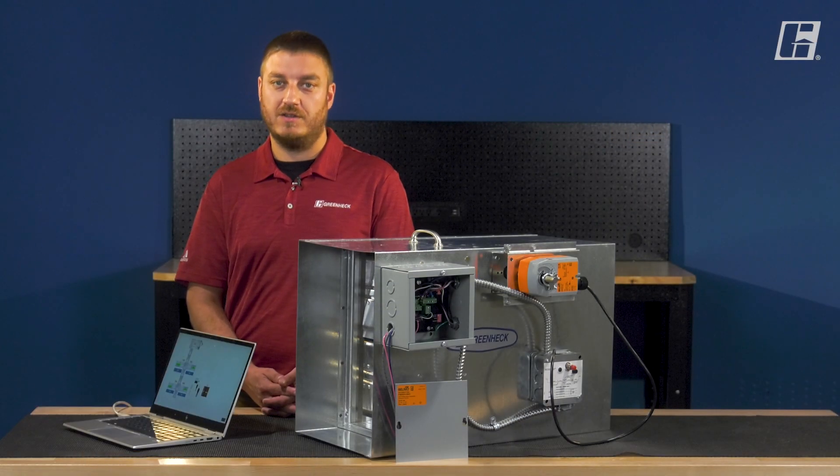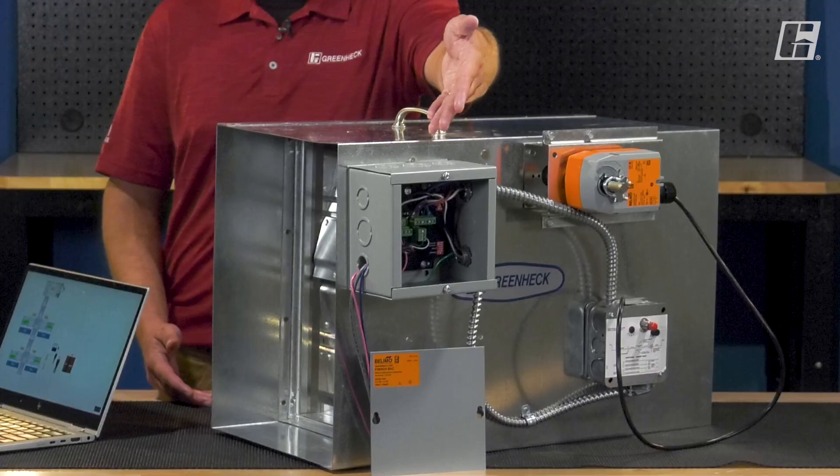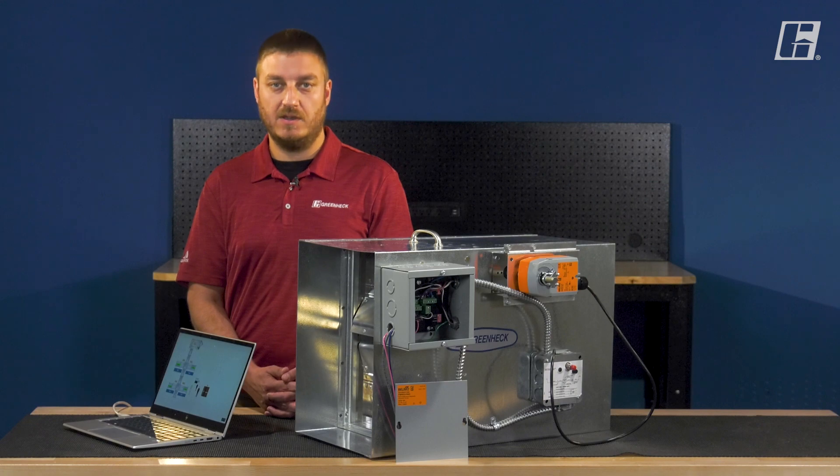Installation is simple. The FSKN is a remote testing module so it can be installed in a convenient location including mounted directly to the damper sleeve. It is available in 24 volt and 120 volt options which also can be used for 208 volt supplies.